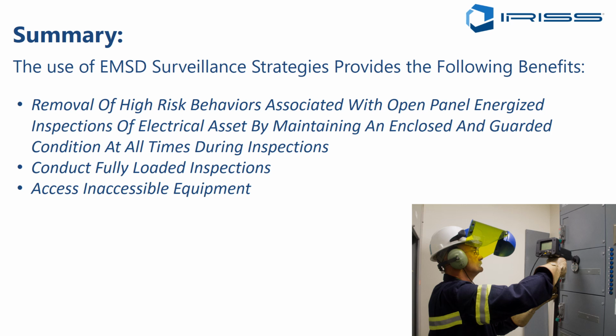We access inaccessible equipment. Something I didn't mention when going through the paper mill scenario was that 17% of their primary switchgear had arc flash hazard in excess of 40 cal, so those were never actually looked at. That doesn't make sense—you need to cover 100% of your electrical equipment because it only takes one piece to knock you out.